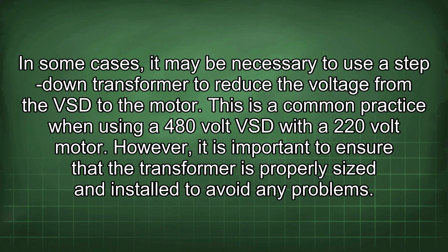In some cases, it may be necessary to use a step-down transformer to reduce the voltage from the VSD to the motor. This is a common practice when using a 480-volt VSD with a 220-volt motor. However, it is important to ensure that the transformer is properly sized and installed to avoid any problems.